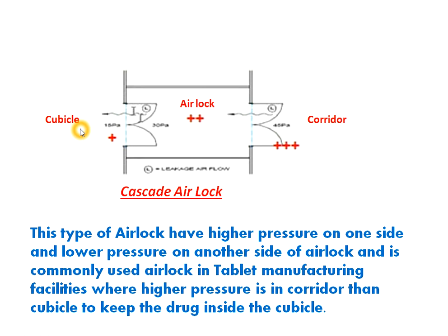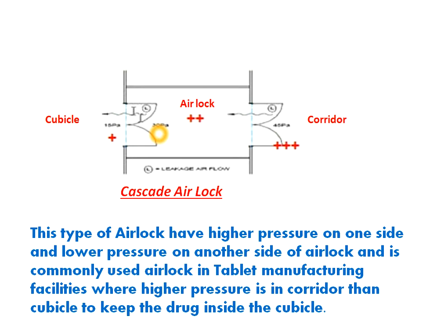Air flows from corridor to airlock and from airlock to cubicle. This is done to avoid contamination — to prevent powder or particles generated in the cubicle from coming out and mixing with the corridor air. If contaminated air reaches the corridor, it can travel to other areas where other drugs are manufactured and contaminate those products. By keeping maximum pressure in the corridor and minimum in the cubicle, air flows inward and cleanliness is maintained. This type is mostly used in tablet manufacturing areas.